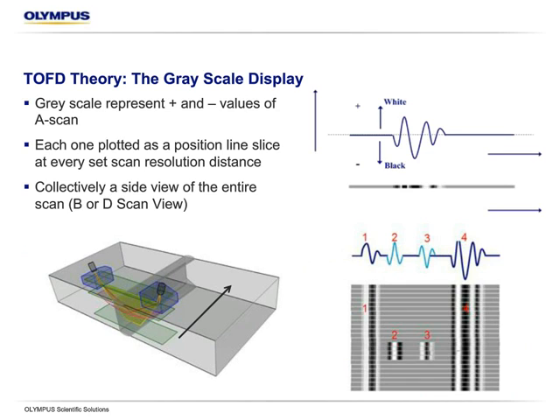So a little bit on the grayscale display. We start with an unrectified RF signal, and then we further manipulate the fact that we can see both a positive and negative component in order to set up very useful displays to investigate large volumes at a rapid rate. If we scan something, we look at every signal, and based on our encoder or our data collection setup, we're basically going to take a strip line of data in black and white format for every millimeter or half millimeter, whatever we set, of movement down that weld. All we do is color code the entire positive and negative scale of that raw signal, and we plot that as a certain tone on a grayscale, typically 128 grayscale, which allows us to have a display similar to that shown in the bottom right here.